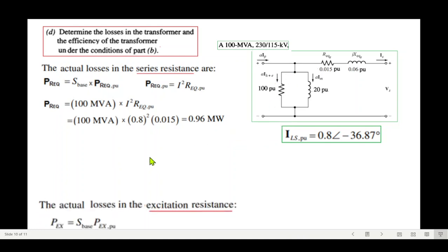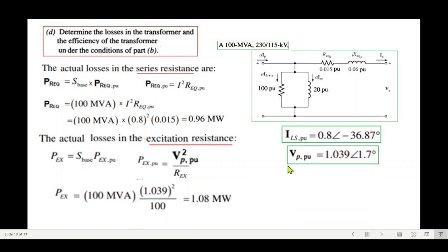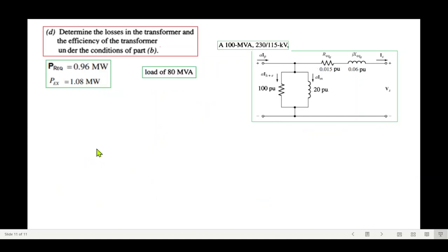The excitation branch loss is P_ex = S_base · (V_P_pu² / R_C_pu) = 100 MVA × (1.039² / 100) = 1.08 MW. So the two losses are: series resistance loss = 0.96 MW and excitation branch loss = 1.08 MW.